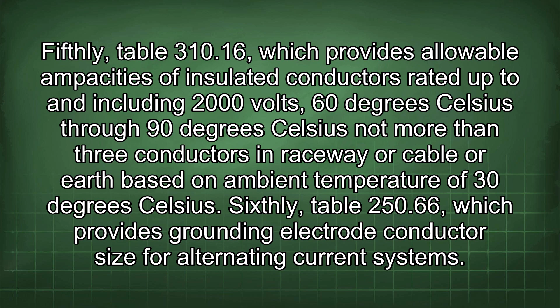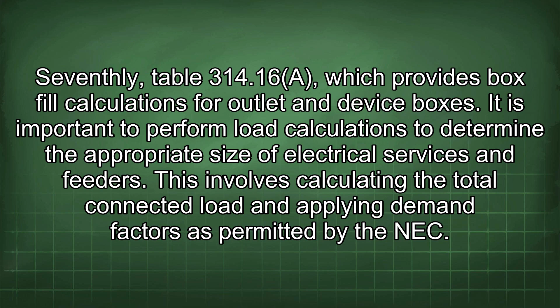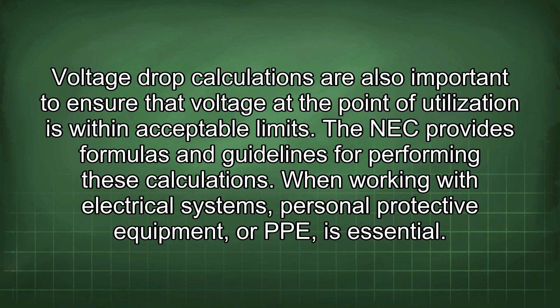It is important to perform load calculations to determine the appropriate size of electrical services and feeders. This involves calculating the total connected load and applying demand factors as permitted by the NEC. Voltage drop calculations are also important to ensure that voltage at the point of utilization is within acceptable limits. The NEC provides formulas and guidelines for performing these calculations. When working with electrical systems, personal protective equipment, or PPE, is essential. This includes items like safety glasses, gloves, and arc-rated clothing. Lockout-tagout procedures should always be followed when working on energized equipment to prevent accidental energization.